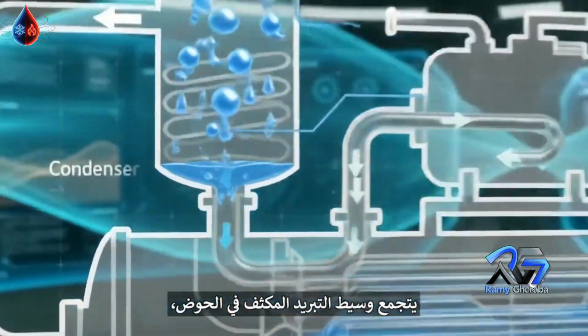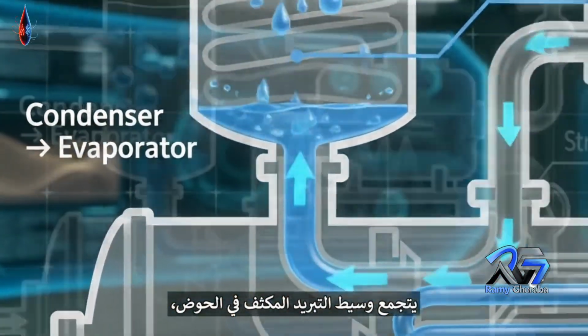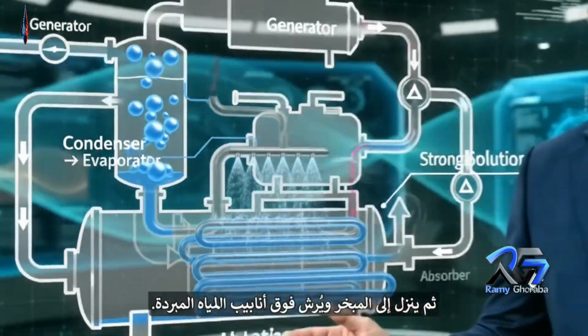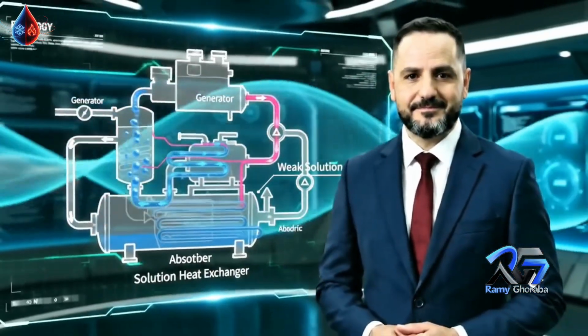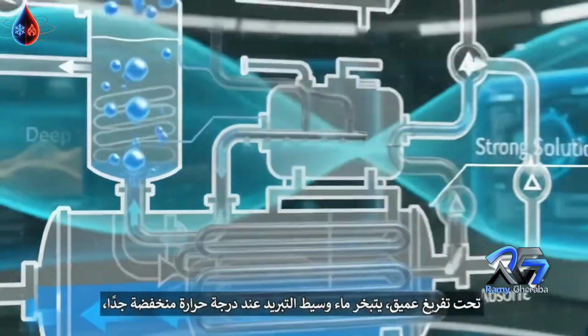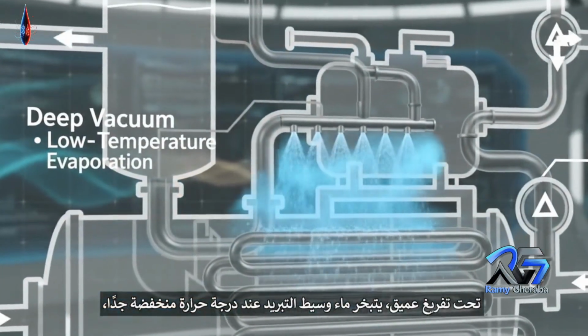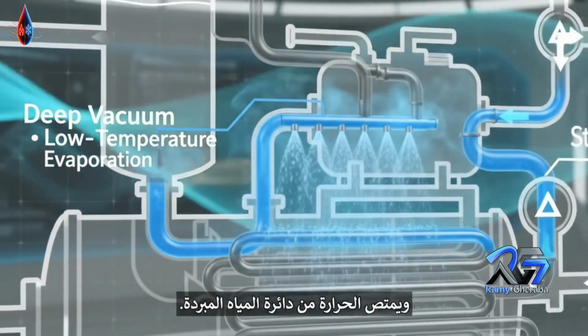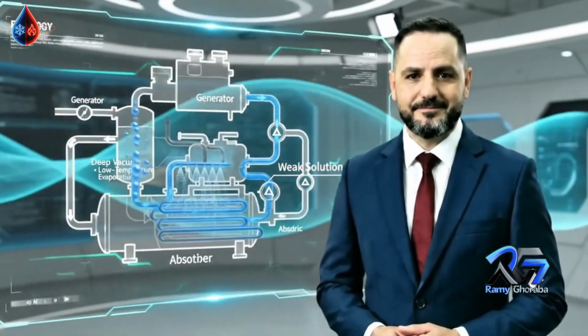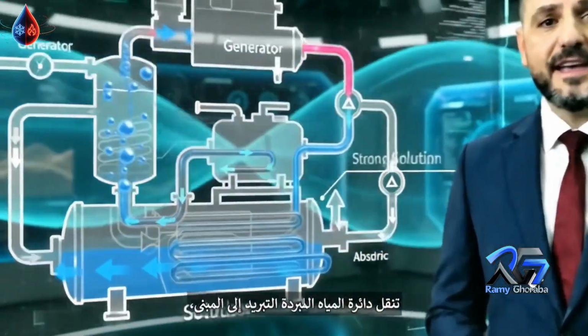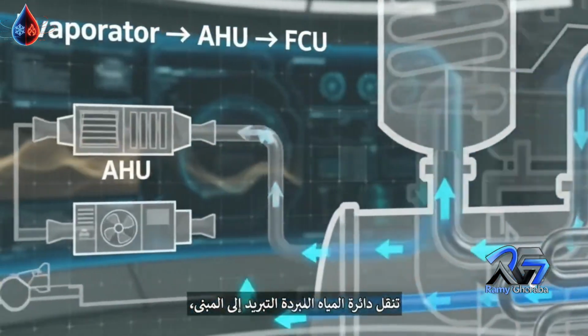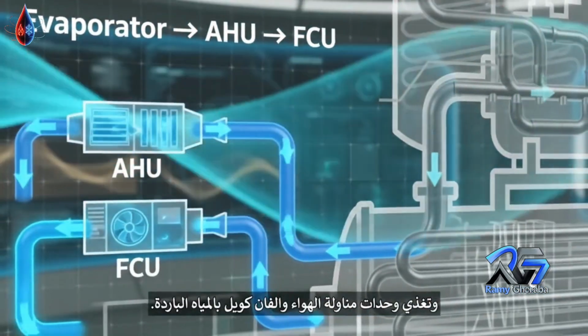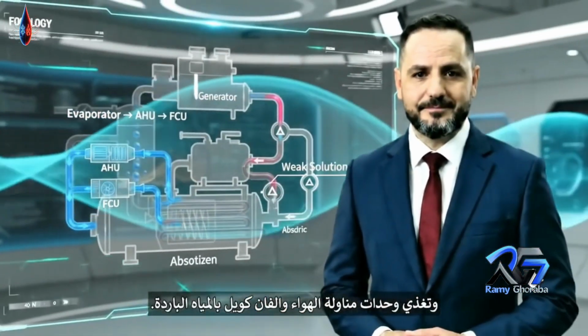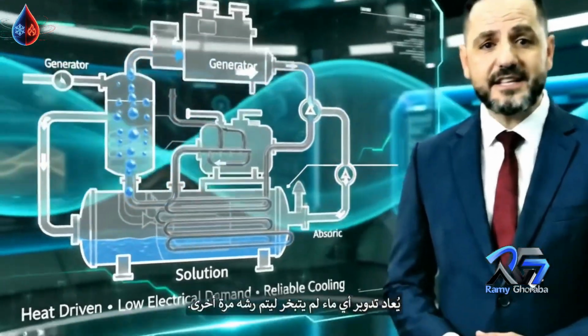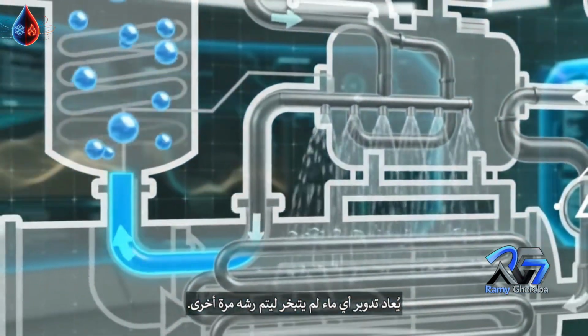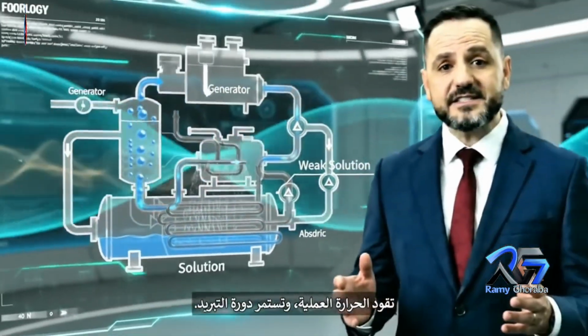Condensed refrigerant collects in the tray, flows down to the evaporator, and is sprayed over the chilled water tubes. Under deep vacuum, the refrigerant water evaporates at a very low temperature, absorbing heat from the chilled water loop. The chilled water loop carries the cooling effect to the building, supplying air handling units and fan coil units with cold water. Heat drives the process, and the cooling cycle continues.